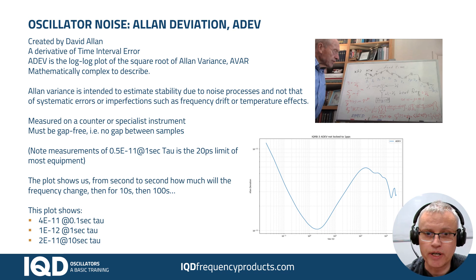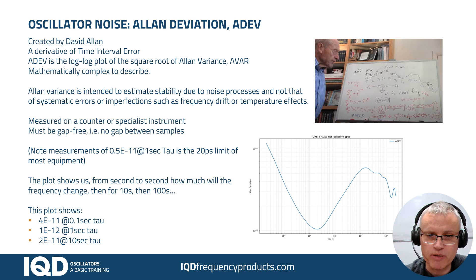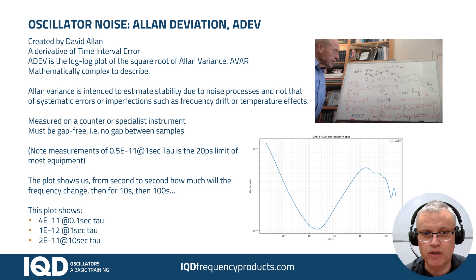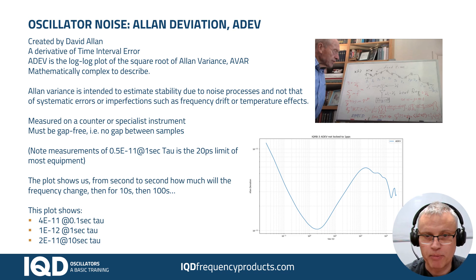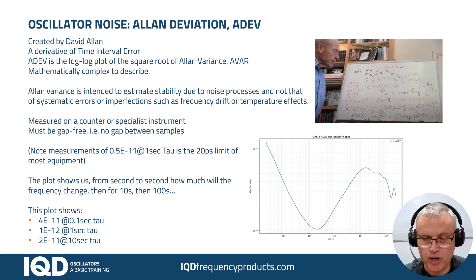To make the measurement you're going to need a specialised instrument or a counter. The measurement has to be made on a gap-free instrument, so it can't be done on a traditional counter — if you have a gate time of 0.1 of a second, there could be a small gap between those two measurement periods, and that was a problem for Allan Deviation. There was a way mathematically to compensate for that but it was very complex. Most modern counters are what we call gap-free, so they're interleaving over each other, which is much easier for an Allan Deviation calculation.